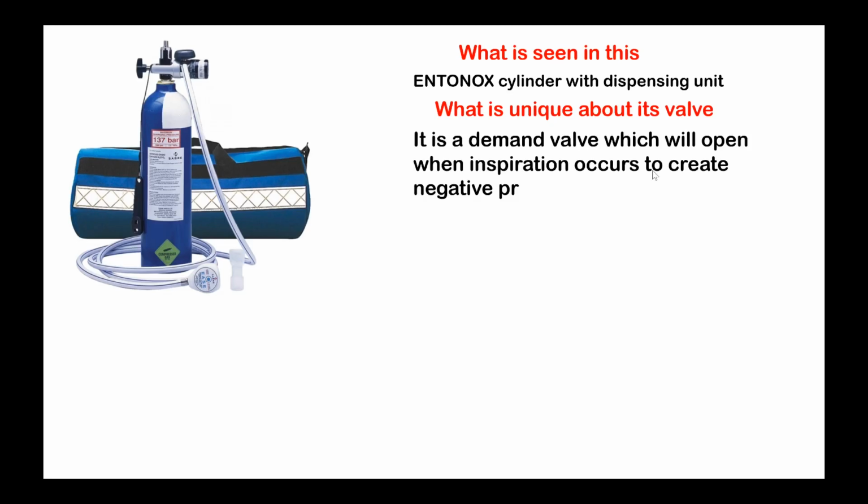The demand valve will open when inspiration occurs and creates a negative pressure. So the patient will inhale only if they take a breath. Otherwise it will not deliver. Like your anesthesia machine is a constant delivery machine. If you open the flow meter, it will continue.